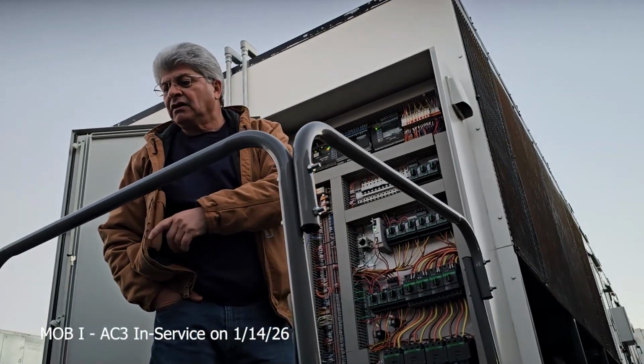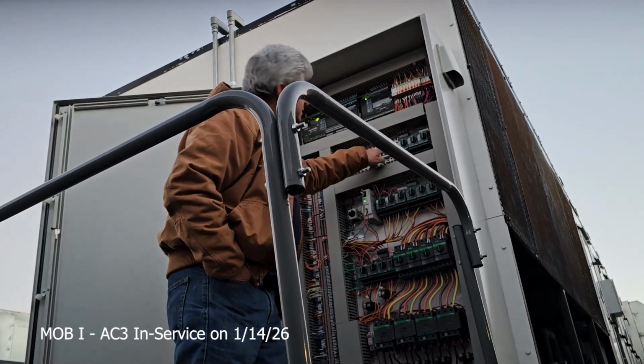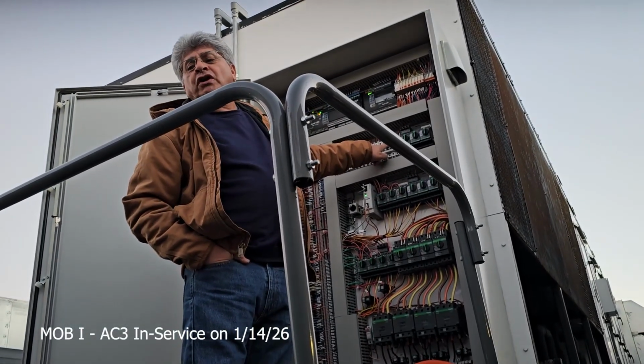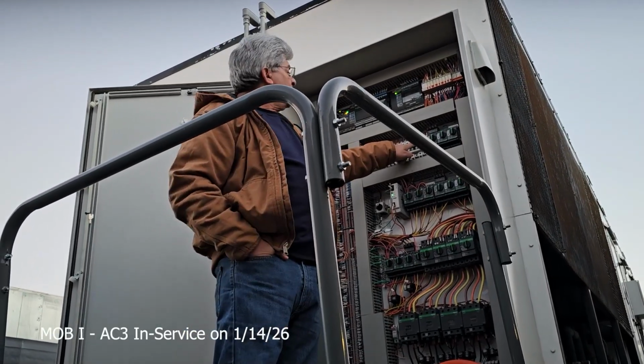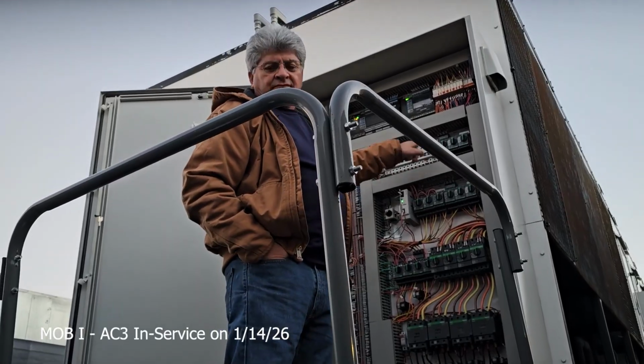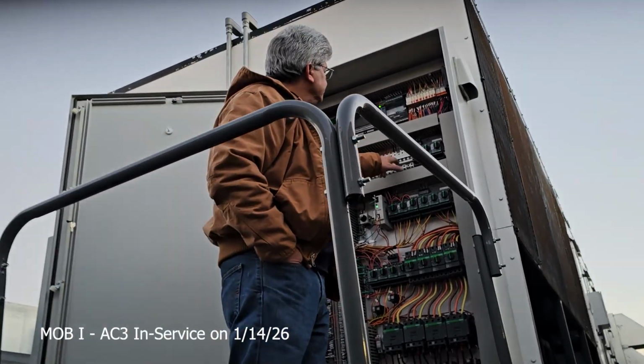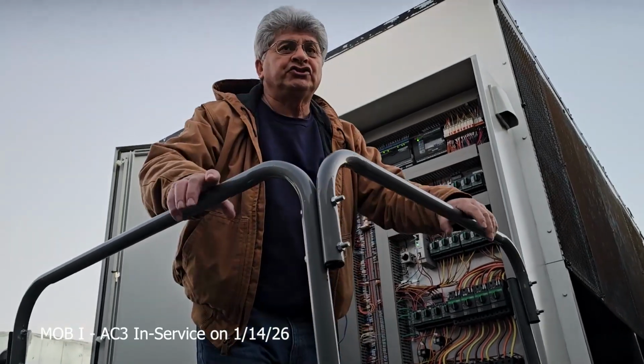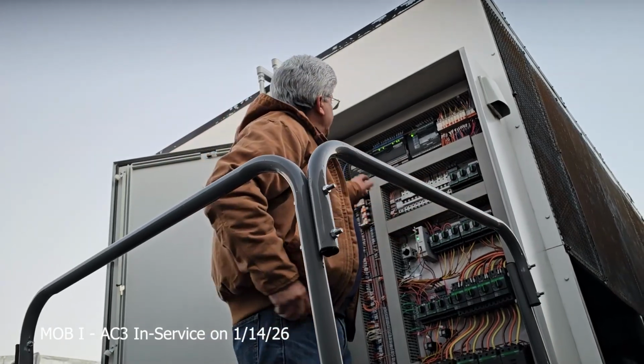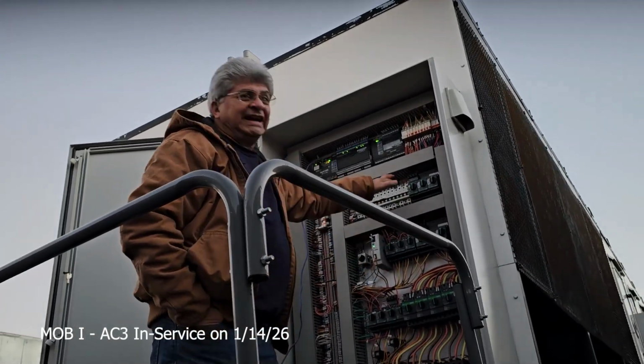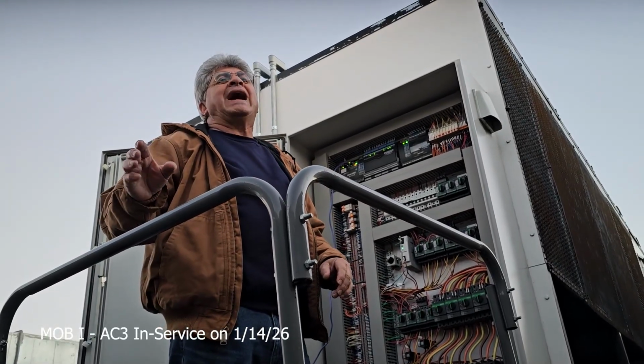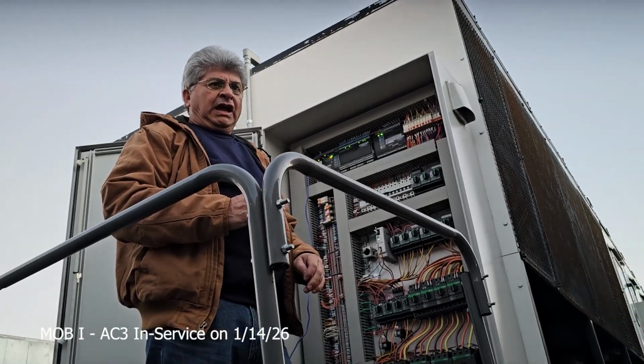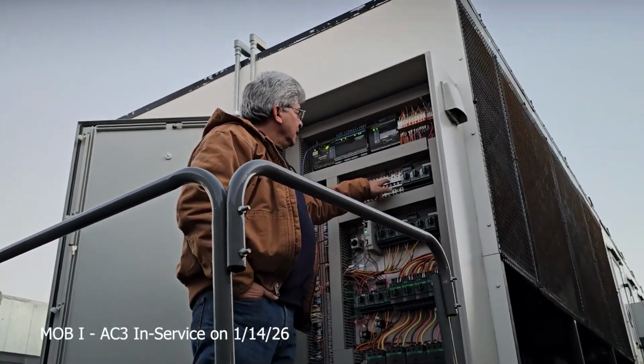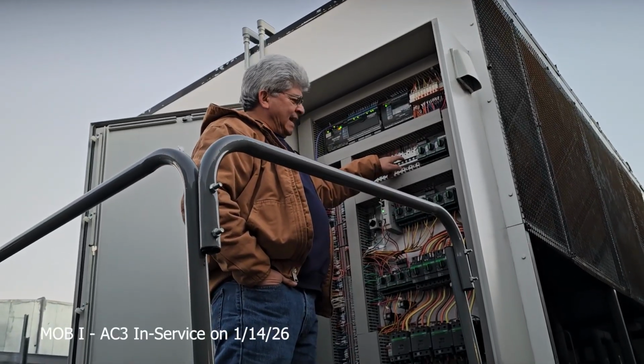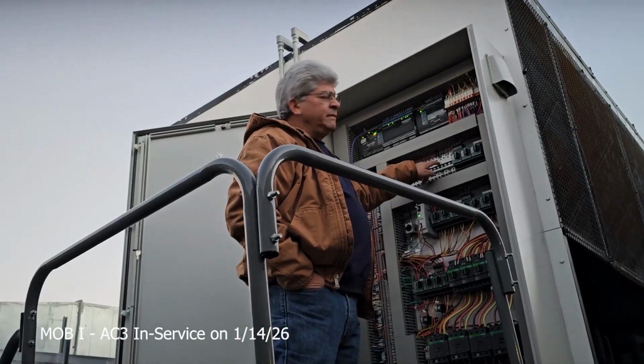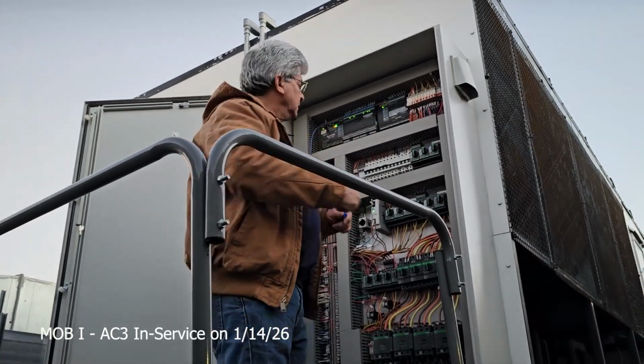Mr. Vicente? What's that breaker number? For what? CB6? For what are you exactly? For your actuators. Is that CB6? CB6, yeah. When in doubt, you can always refer to the wiring diagram. CB6 shuts off the control voltage to your actuators. So by shutting off this switch and all this, it still leaves power to your actuator. Okay. Maybe we should mark that one. Something. Yeah, that would be good to make a little note up here. Like a Sharpie? Yeah, all that would be on your wire diagram.